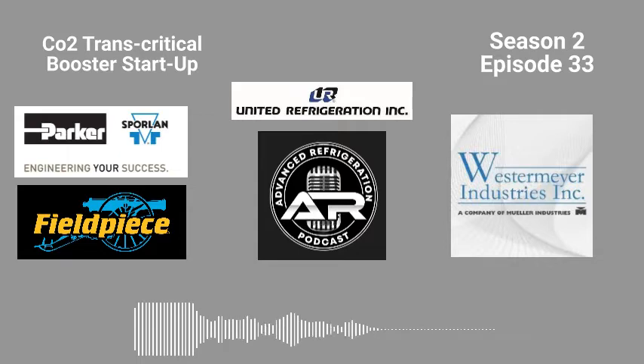I'll get a little bit of liquid in there. Then what I will do is start dumping it into the case side of the actual line. It really depends. If I can get it all in the flash tank and it's going to take it, then I'll keep dumping it in the flash tank. If I have the ability to feed it out to the cases and let it come back to the compressors, I'll do that because it's way faster. So what I've been doing is putting a packed angle valve.